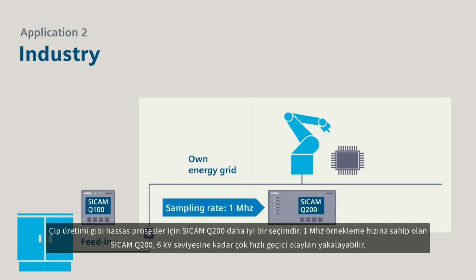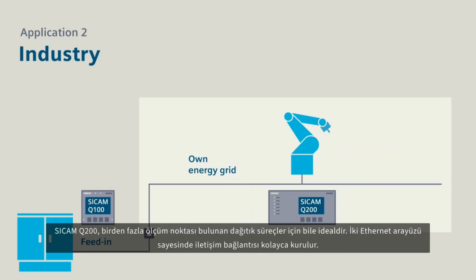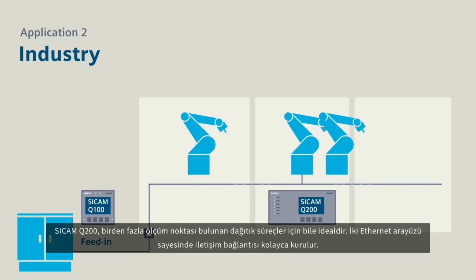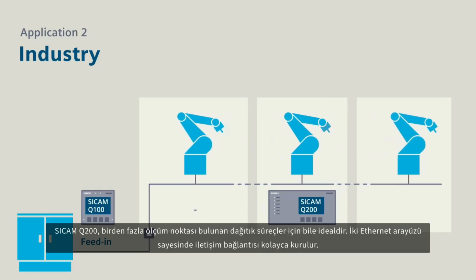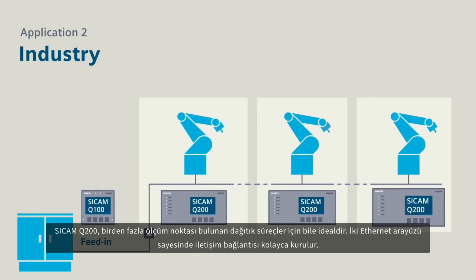For sensitive processes such as chip manufacturing, it is better to use a SICAM Q200 with a sampling rate of 1 megahertz. The SICAM Q200 can also acquire extremely fast transients up to 6 kV, and is optimally suited even for widely distributed processes with multiple measuring points.